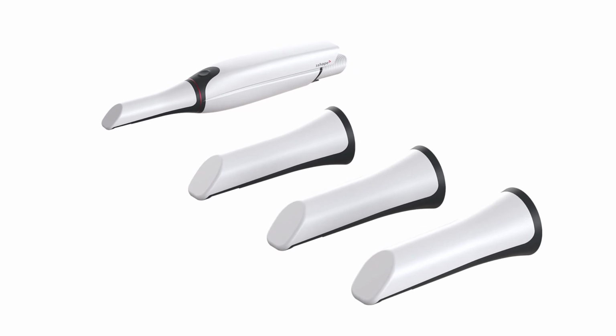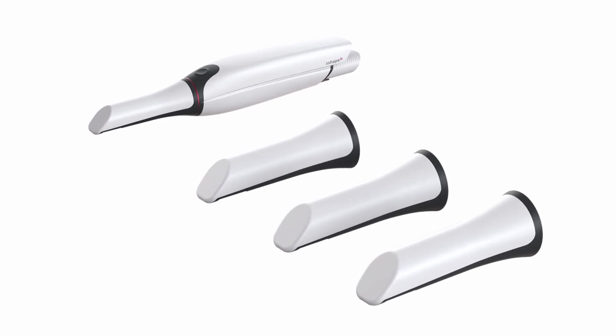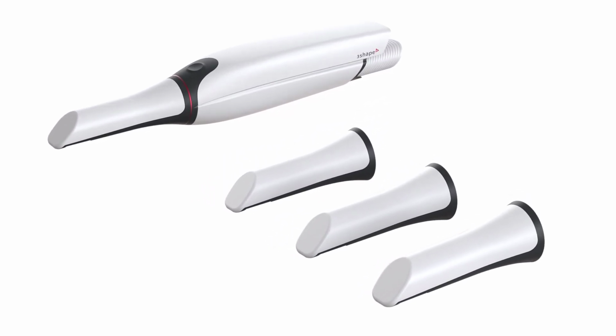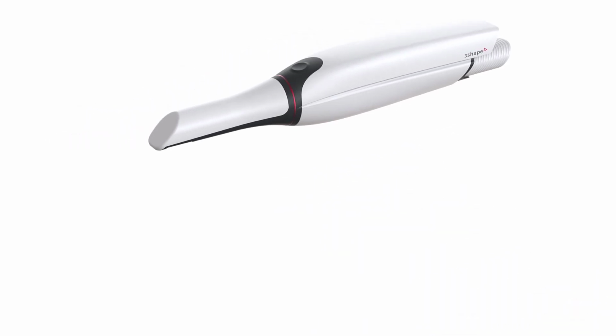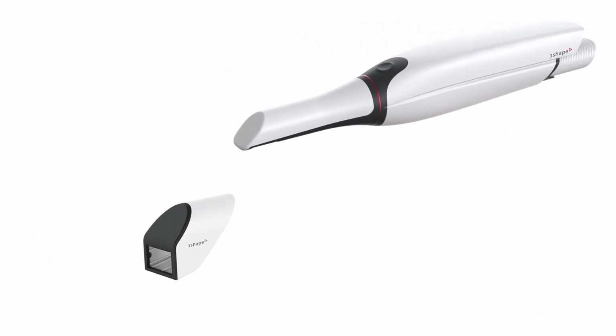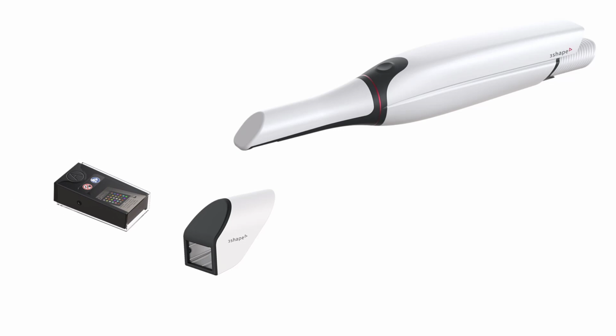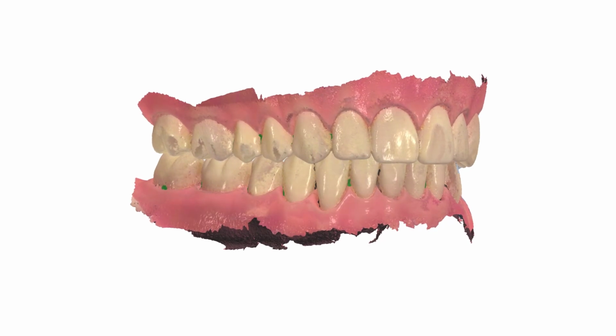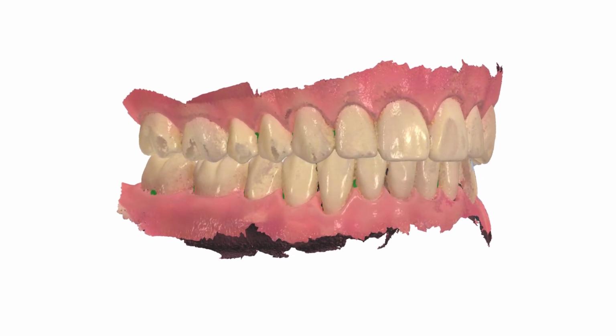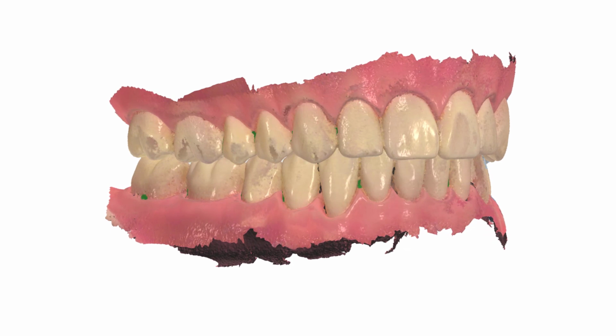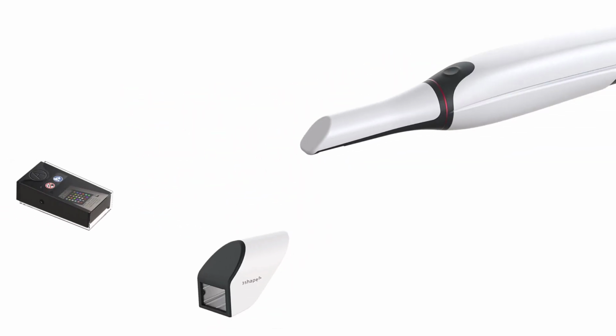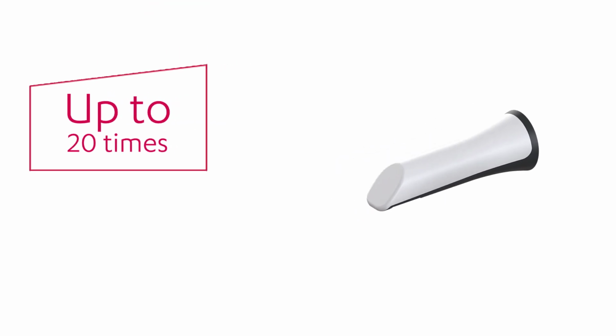All new tips delivered with your TRIOS 4 are already calibrated, so you can start scanning right after sterilization. However, all new tips bought as spares need to be calibrated before first use to assure the best scanning results. Skipping calibration, although possible, might impact the color accuracy of the scan. After calibration, each tip can be used for scanning up to 20 times before the next calibration.